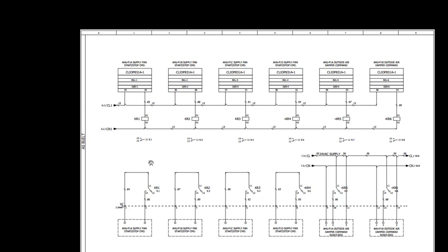That's why we used a relay for safety. Otherwise my panel relay would be damaged. So if your module supports 24 volt and 230 volt AC and the contact ratings are enough, then you may not find this relay in your panel, and the command will be directly connected to the terminals. But in our case it is the opposite.